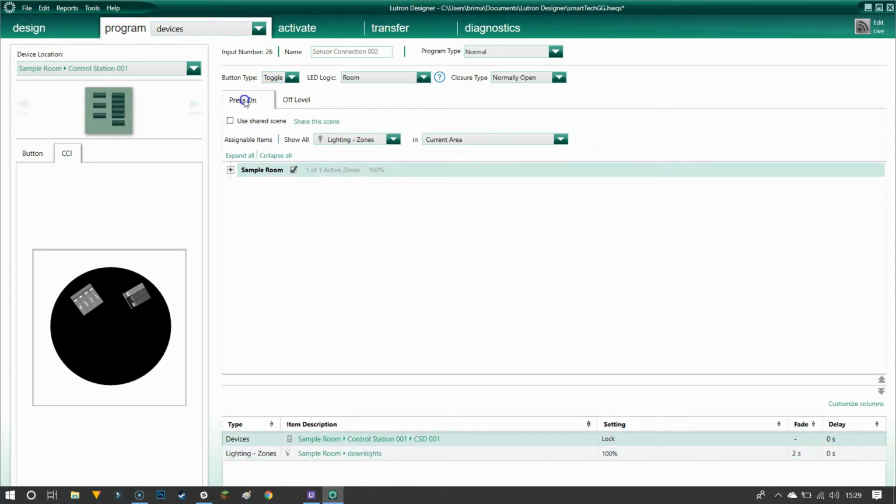So this is a very basic scenario where you can tie in a third-party PIR to a keypad. And it's as simple as that. You just literally wire your two connections back to the PIR contact closure outputs. This has to be a voltage-free contact, ideally. So a voltage-free contact. And that's as simple as it gets. So let's just untick that quickly.